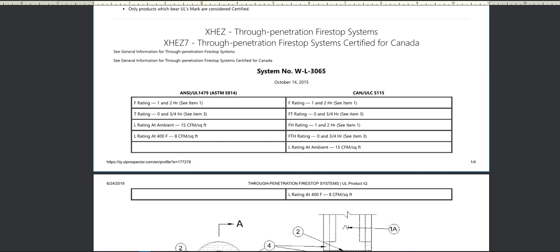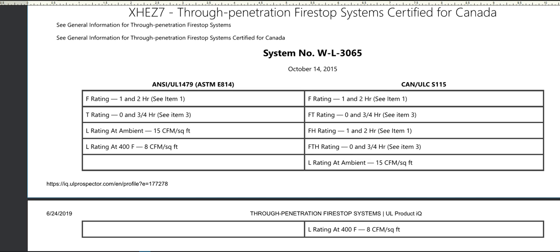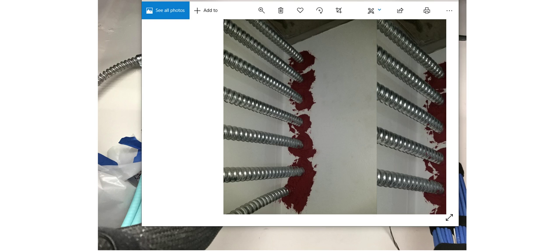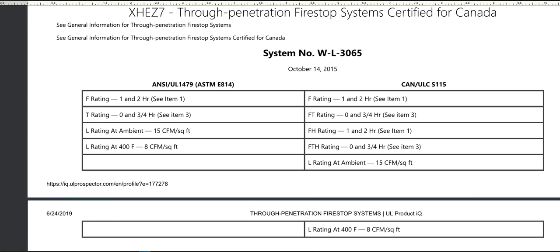WL 3065 is a very versatile system that allows many different configurations — sleeves with cables, low voltage or electrical, bare cables, smaller sleeves or penetrations. There is a whole separate video series on how to read the nomenclature of a fire stop system. In this case: W for wall, L for framed wall, and 3 for the cabling system — specifically the 65th cabling system. Right away from my photos I'm able to match up and say I've got cables going through a wall.